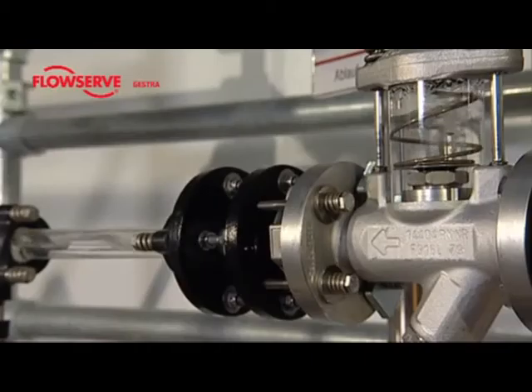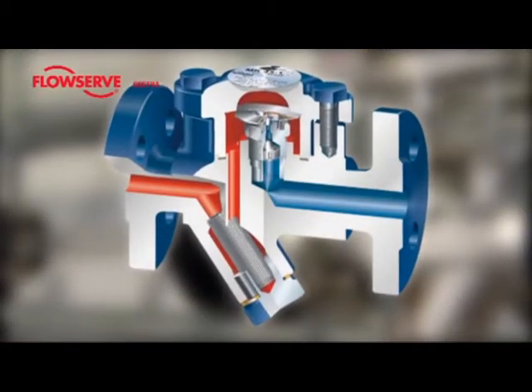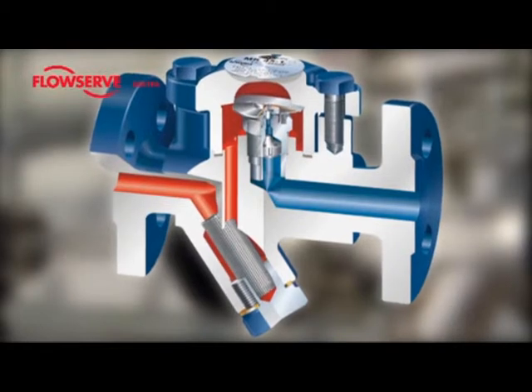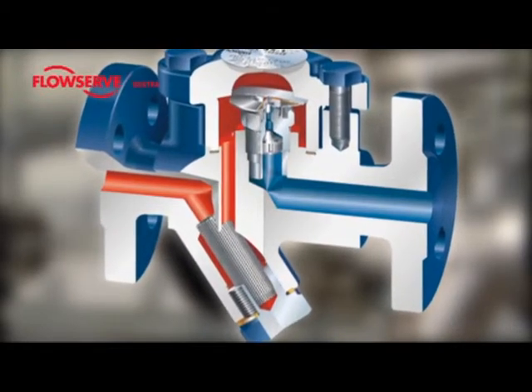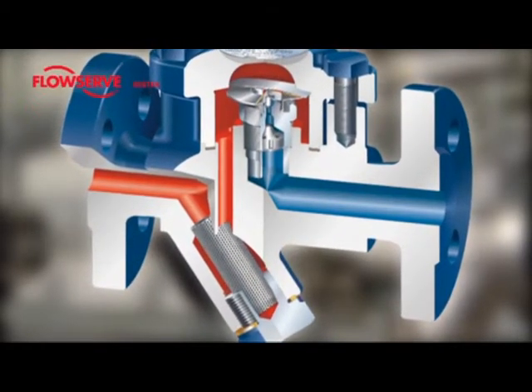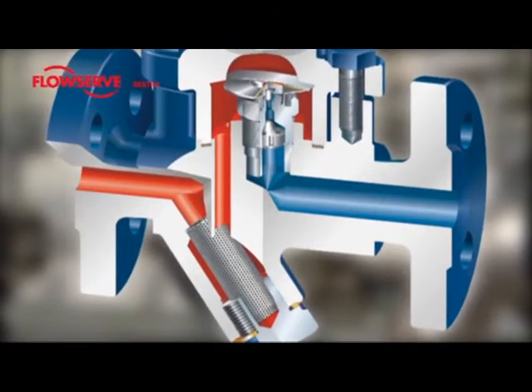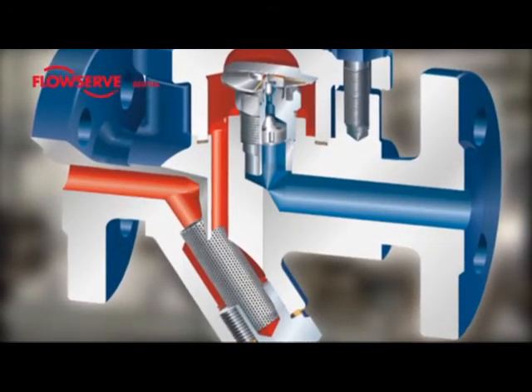The condensate from the heat exchanger flows through a strainer in the steam trap's cover, in which a membrane regulator is installed. When the steam trap is open, the condensate can pass through a hollow cone, a non-return valve to protect the capsule against water hammer, after which it flows to the outlet.